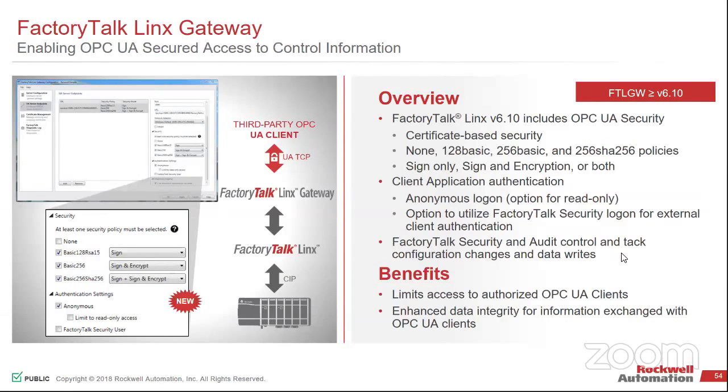There's a couple other usability enhancements that they've made. So I would recommend, even if you're used to RSLinx Classic and you're dead set on using it, I'd give regular FactoryTalk Linx a shot, just because some of the usability things they've added is the ability to auto import your drivers. So no longer will you have a little yellow circle when you're browsing through. It'll auto grab EDS files and your ability to copy and paste, essentially export your IP list and import an IP list.